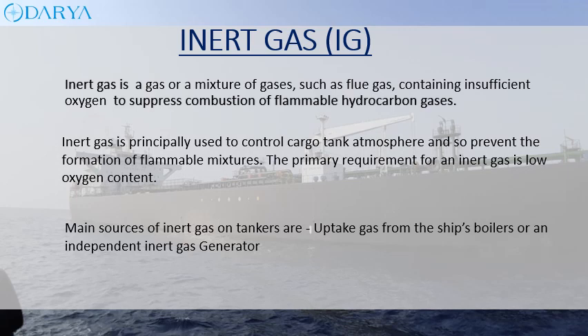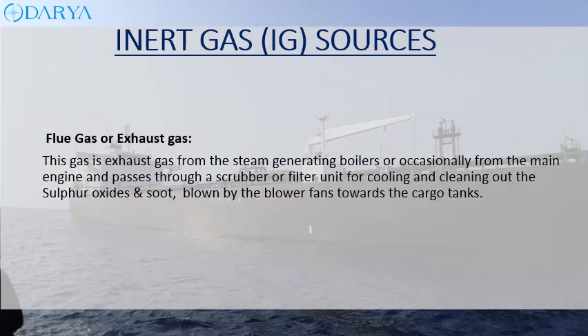The main sources of inert gas on tankers are uptake gas from the ship's boilers or an independent inert gas generator. Flue gas or exhaust gas is exhaust gas from the steam generating boilers, or occasionally from the main engine, and passes through a scrubber or filter unit for cooling and cleaning out the sulfur oxides and soot, blown by a blower fan towards the cargo tanks.